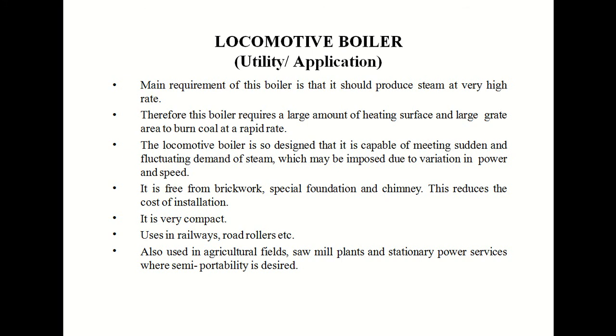So, utility and application of the locomotive boiler. The main requirement of this boiler is that it should produce steam at a very high rate. We already discussed that; it has a very high rate of steam generation, 9000 kg per hour. Therefore this boiler requires a large amount of heating surface and a large grate area to burn coal at a rapid rate. If we require a large amount of heat generation, obviously the heating surface area will be required to be higher. Whenever you increase the grate area, rapid burning of coal will take place.